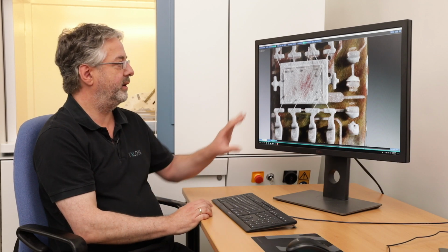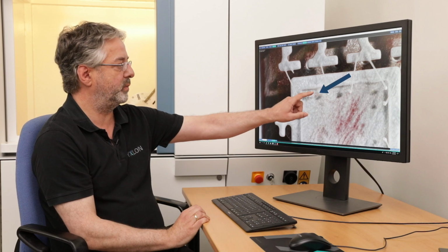If you have prepared your transfer functions, if you have a good region of interest for your sample, this is what your manager wants to see. He wants to see a good image which explains everything. It's easy to use. You can zoom in. And then you can see the blown wire here. Here's the rest of the ball bond also here.